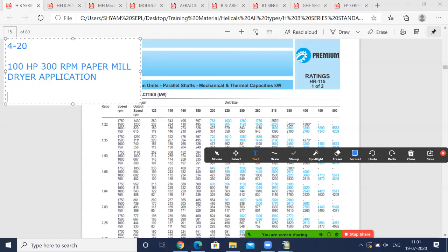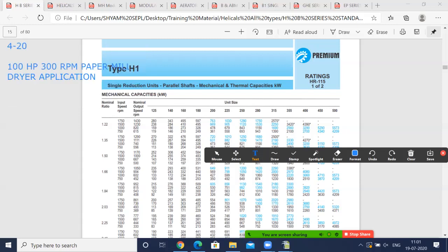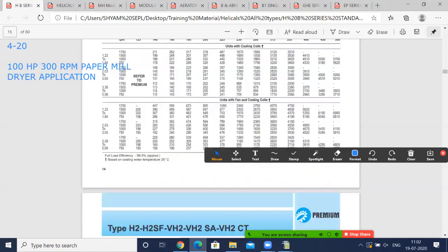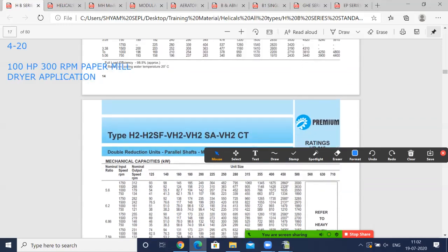Here you can see the different motor speeds. For each motor speed, you first have to check whether the motor speed is 1440, that is a normal 4-pole, or it is a 6-pole. Suppose it is a 4-pole motor. In paper mills 6-pole motors are also used, so you need to be very clear before you start the selection.